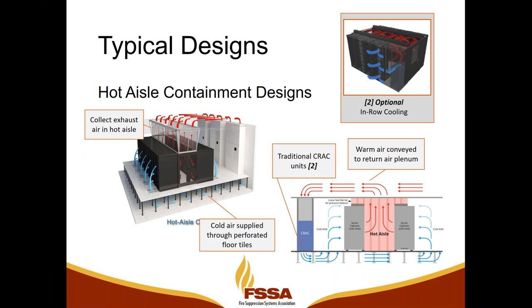Again, a variant to highlight in this case is in-row cooling. There are some data centers that use close coupled in-row coolers to cool the air immediately around the pod that is built with containment. And so it sucks air out of the hot aisle, cools it down in a unit that's sitting directly adjacent to one of the racks or amongst a row of racks, and then blows cold air, which can be sucked back into the hot aisle again in a continuous loop. So that's, again, a variant of hot aisle containment.